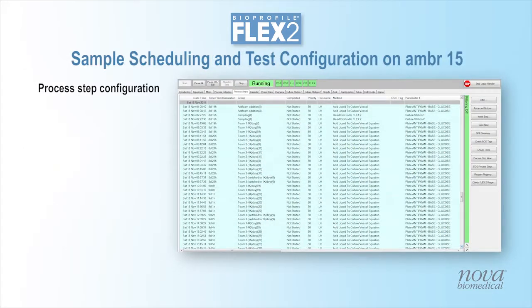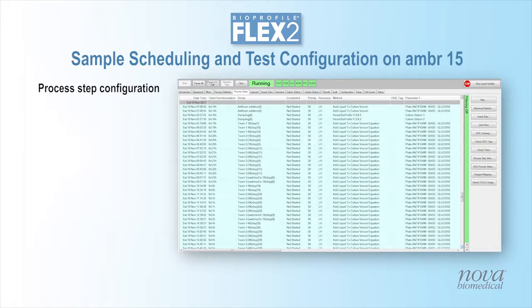Sample scheduling and test configuration are performed via the ambr 15 user interface. New process steps can be created or existing process steps modified to schedule sampling of each micro-bioreactor followed by analysis by the Flex2.